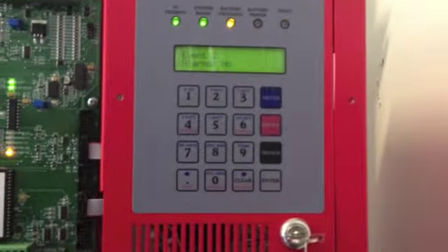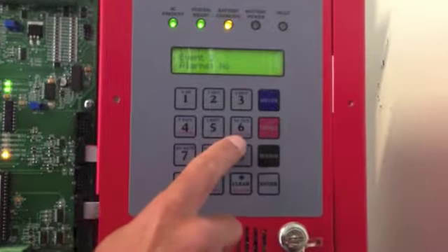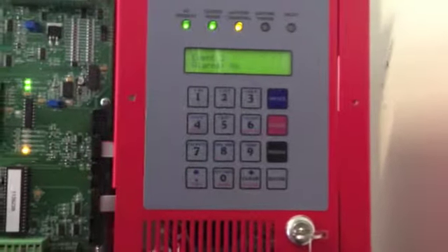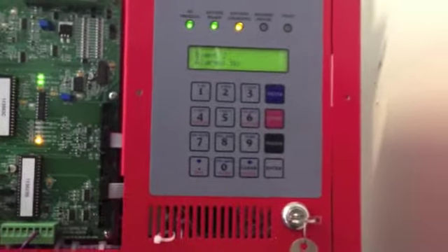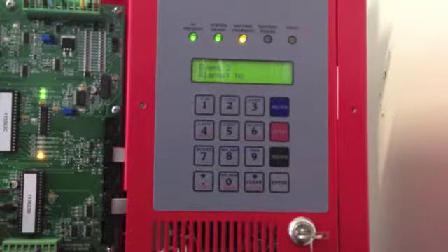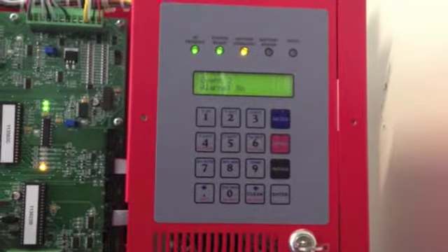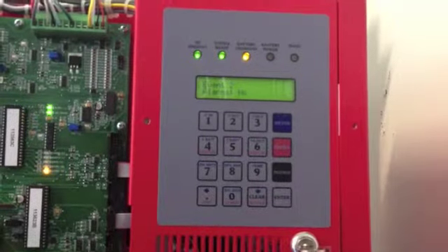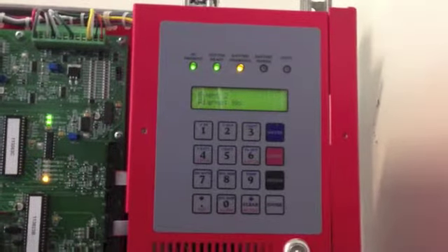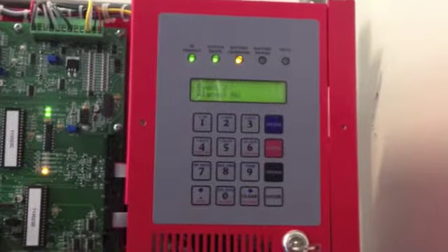So that's acceptable. So the difference when we're looking at test and event log: test log, always no alarms because there's never a power failure. Event log, an alarm condition is okay because that's typical with a utility failure. We just need to pay attention to how often it's transferring and for how long.